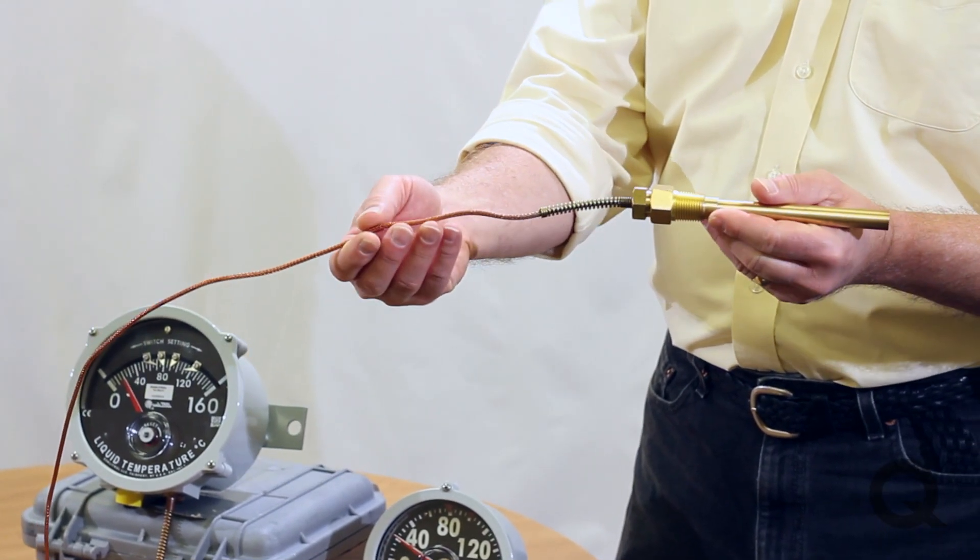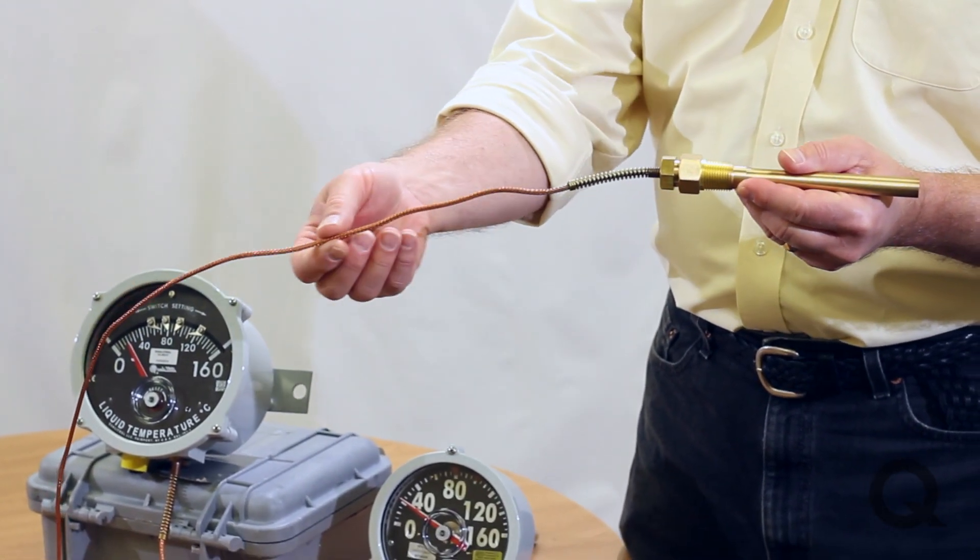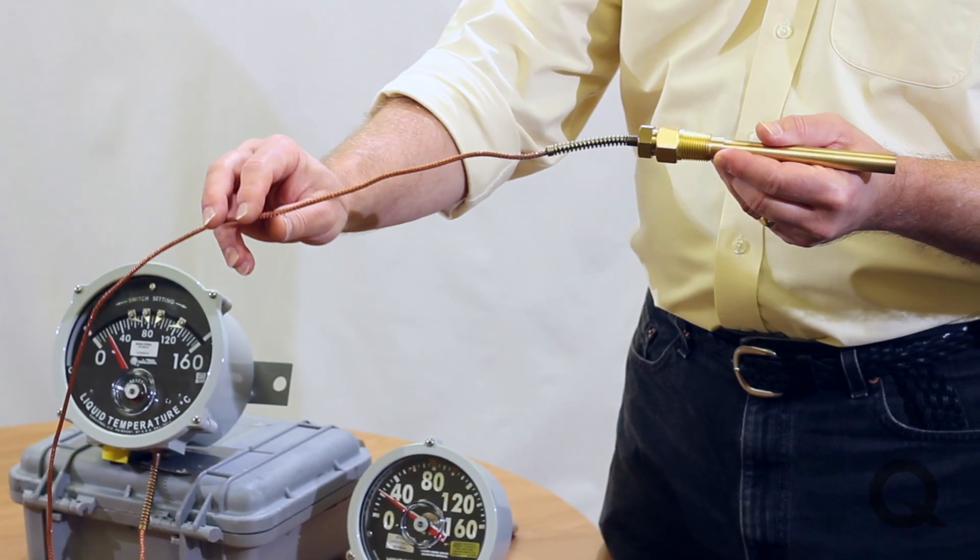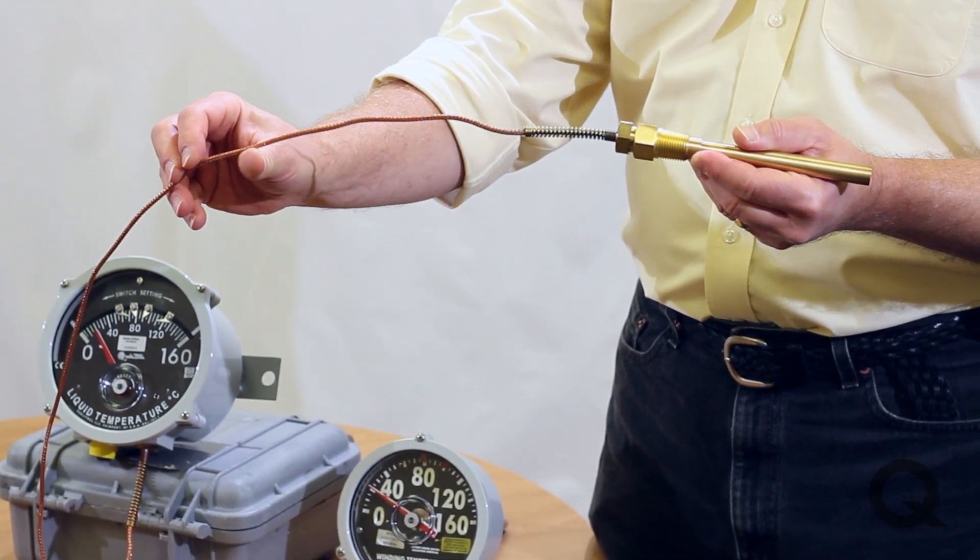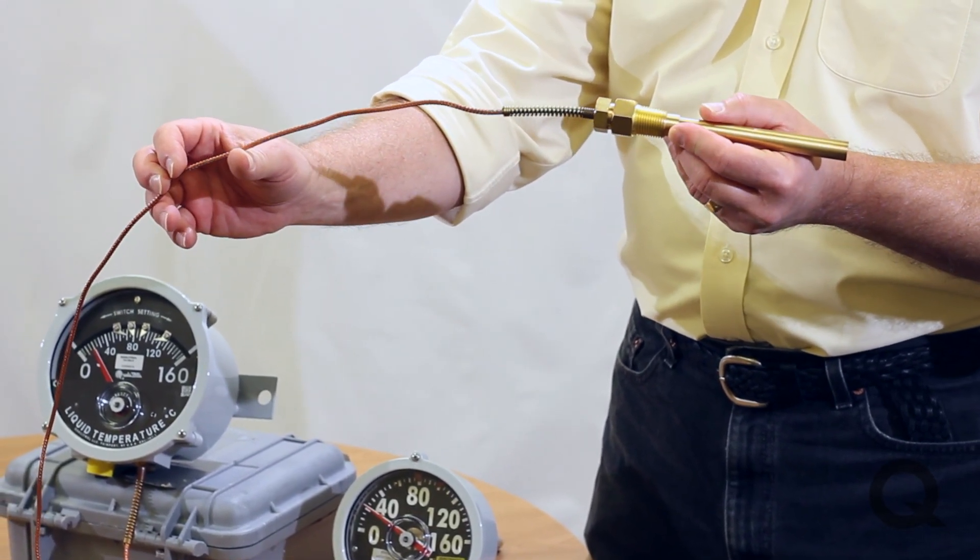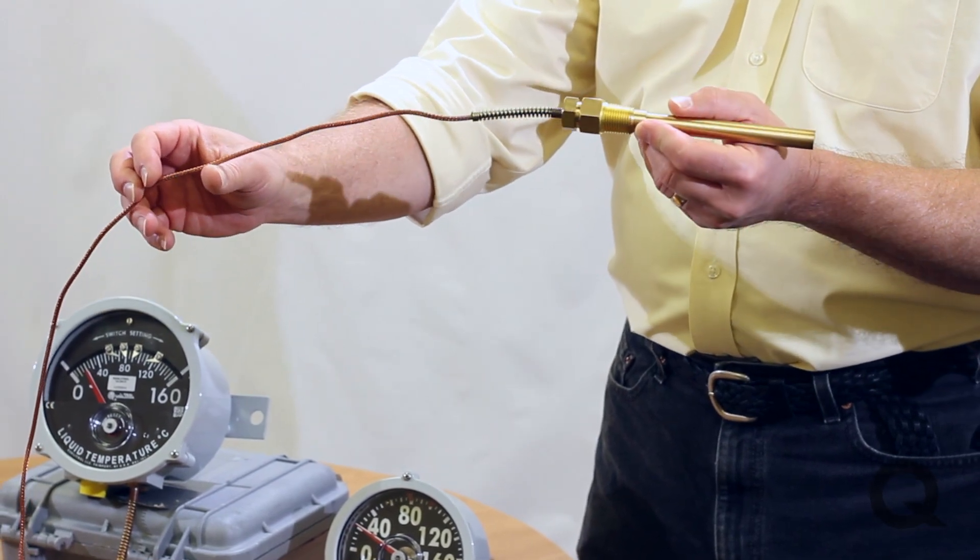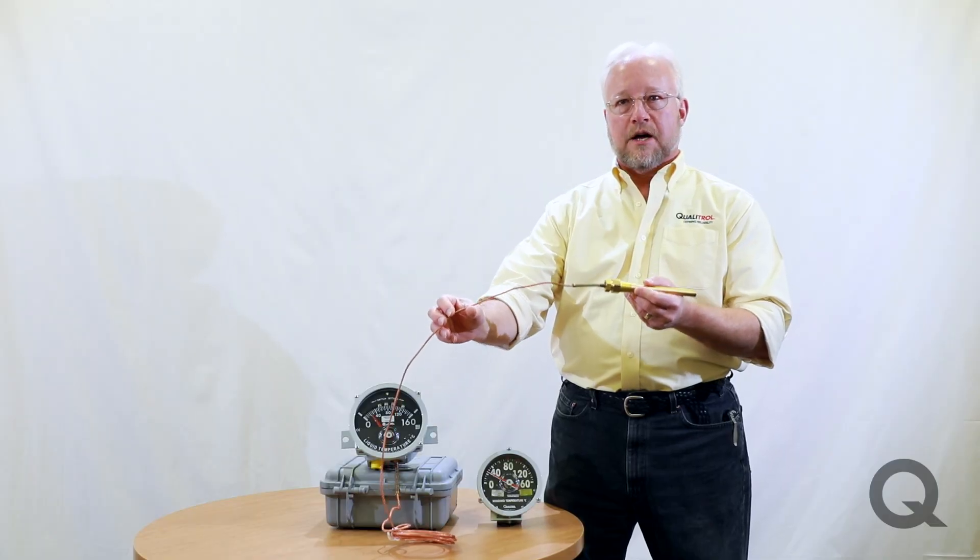The other thing with the capillaries is that you want to be careful with the capillaries. Do not bend them tighter than the radius of a full can of Coca-Cola. If you kink the capillary, if you cut the capillary, the thermometer is going to be ruined. So you don't want to do that.